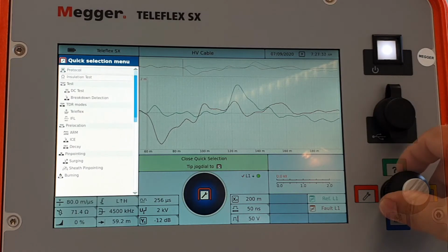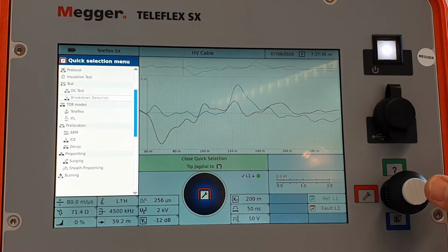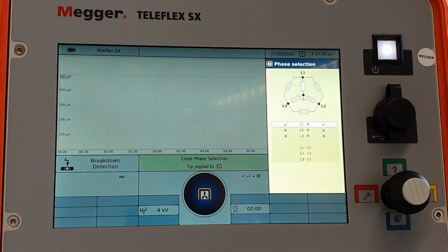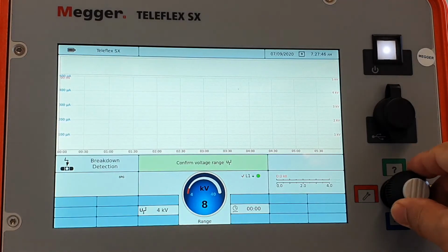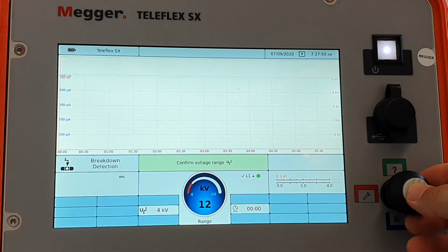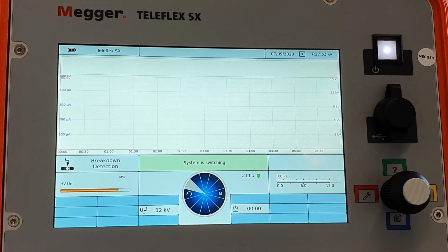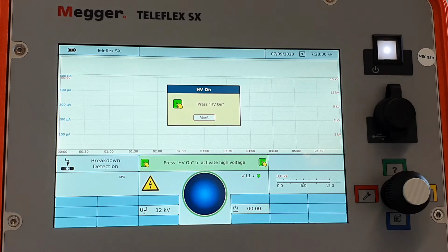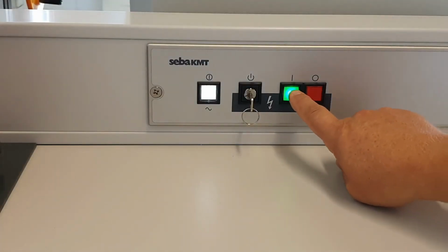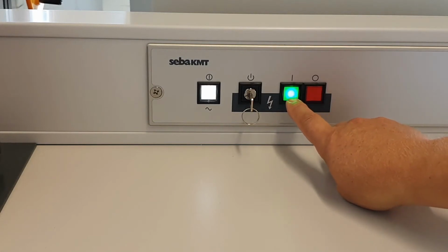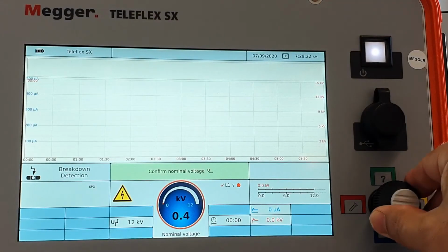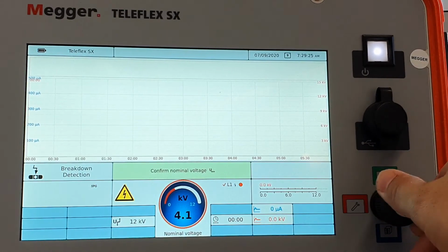I will go into the breakdown detection mode to find out what is my breakdown voltage. It automatically jumps in the phase selection. I accept that, close that window. I give it a bit of voltage, the maximum voltage that I dare to apply. Start. And here you hear the automatic switching inside the unit. And now I have to confirm by pressing the green HV on button. This is to consciously confirm that I do apply high voltage now. It has to be a separate hardware button, so you cannot interfere with any software there. I can now fine adjust my voltage within a range.